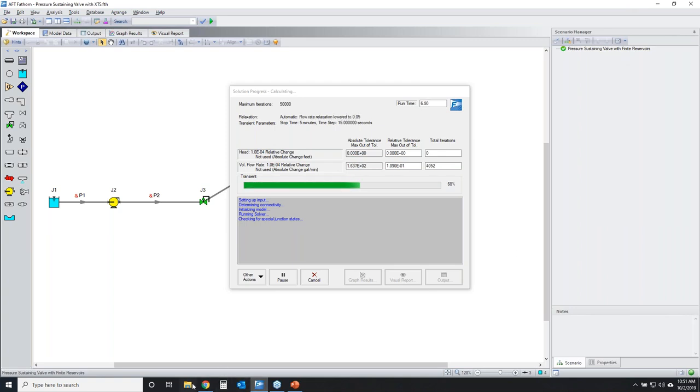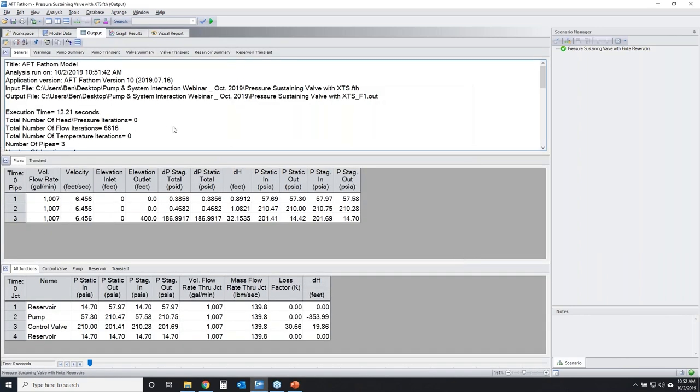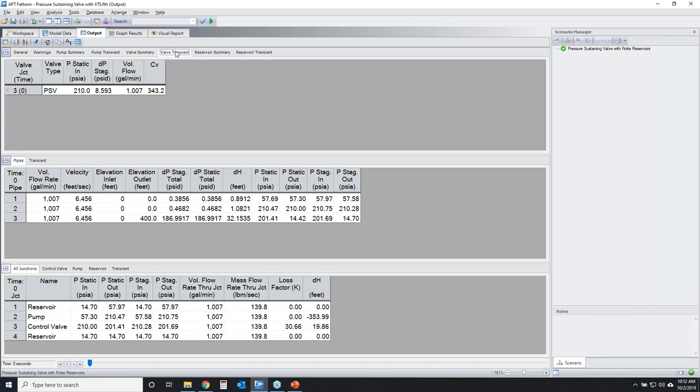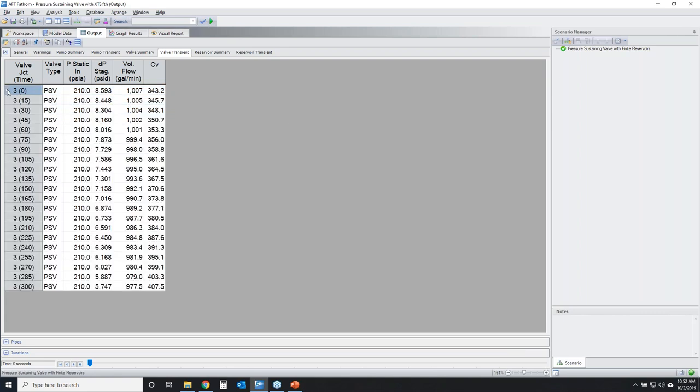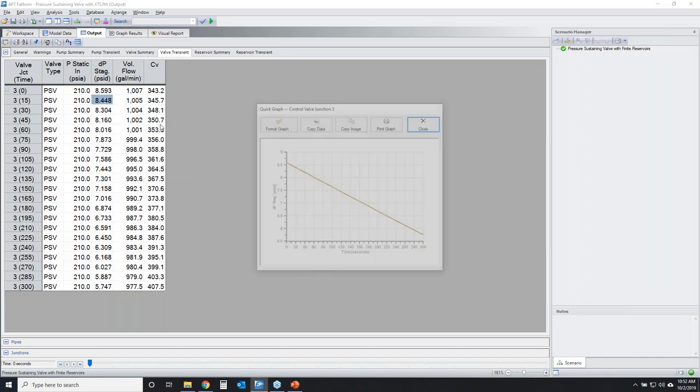Now, while that's running, I'm going to open up one of my folders here on the side. All right. The first thing that we want to take a look at is how that pressure sustaining valve is changing. If I go to the valve transient tab, this is looking at the very first data point at time zero. I want to expand this. As we can see here, at every single time step, our set point is exactly the same, but the CV value is changing and the pressure drop is also changing, as well as the flow.